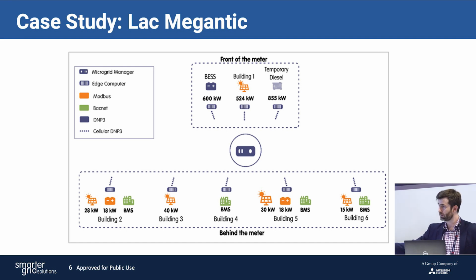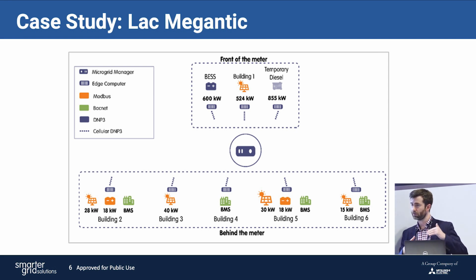Beneath that, we have a variety of behind-the-meter devices. There's a number of smart buildings connected, each with some mix of rooftop solar, maybe storage in the basement, as well as building management systems. A BMS is a controllable building, one where you can dial back the thermostats and give it a kilowatt set point for how much power to give or reduce, or just say turn off the boilers X% and get an undefined amount of power in return. All of these have to come together to balance the energy mix and make sure we're net zero on our microgrid, because when we're islanded, we can't draw any power from the grid.